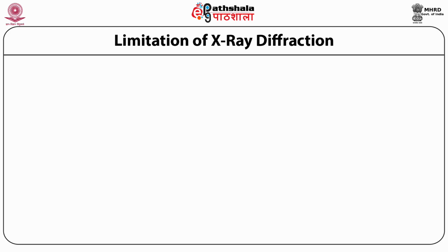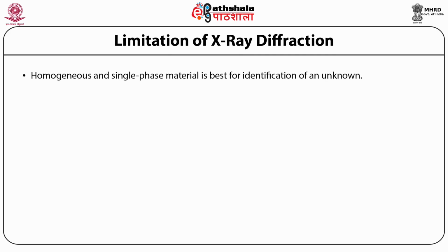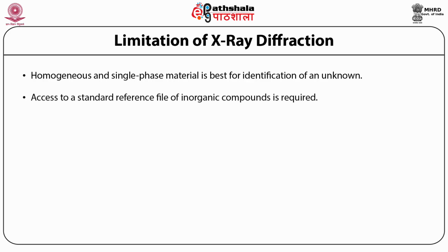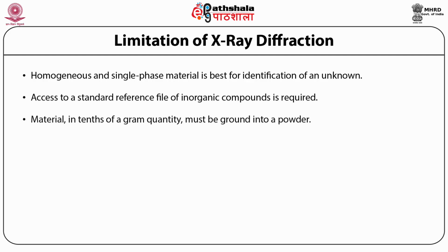Now, we will talk about the limitations of X-ray diffraction, which are as follows. A homogeneous and single phase material is best for identification of an unknown, and access to a standard reference file of inorganic compounds is required. Material in tenth of a gram quantity must be ground into a fine powder. For mixed materials, the detection limit is approximately 2% of the sample.